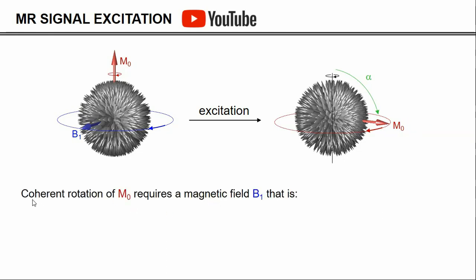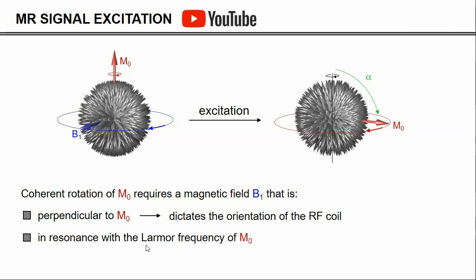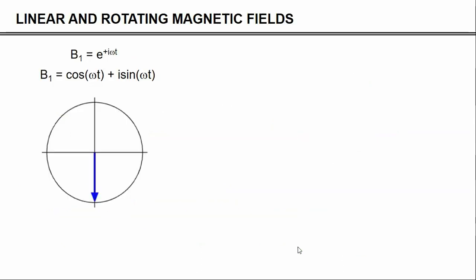So, the coherent rotation of the magnetization requires a magnetic field B1 that is perpendicular to M0, and this ultimately dictates the orientation of the radio frequency coil that will produce the radio frequency pulses, and it requires the B1 field to be in resonance with the Larmor frequency of the spins. In other words, B1 is a magnetic field that rotates at the Larmor frequency.